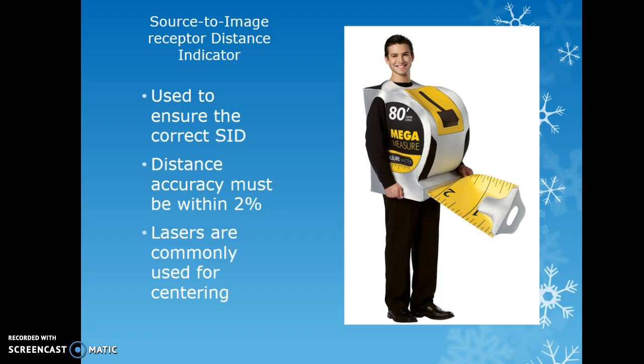The source-to-image receptor distance indicator is essentially the measuring tape, used to ensure the correct SID, which affects technique selection. Distance accuracy must be within 2%, so a broken tape measure cannot be used as a guideline. Lasers are commonly used for centering, along with the collimating light.